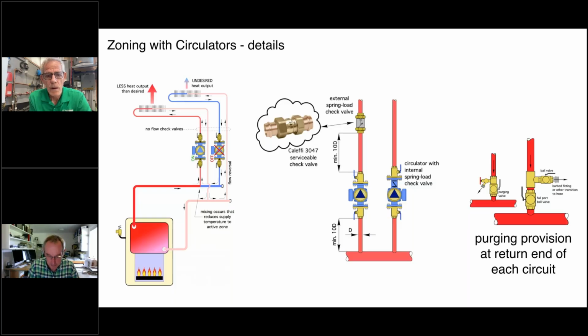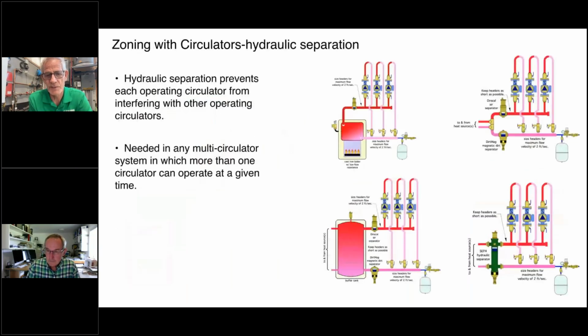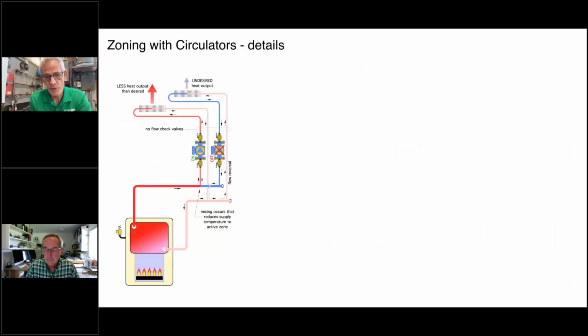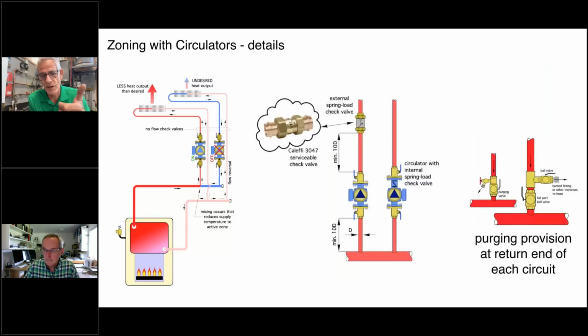So those are just a couple of details when you're zoning. And by the way, if you're zoning with zone valves, I would still suggest these are good details on the return side of the system. Those little valves with the side port and the hose connection are a good place to inject chemicals into the system too, because it is a ball valve with a hose cap, and Fernox and some of the other brands make an aerosol can that screws right onto that, and you can squirt some conditioner or cleaner into your system. So it's a nice access port.